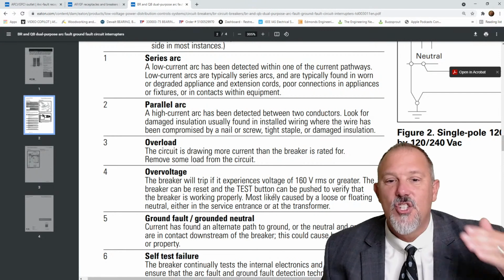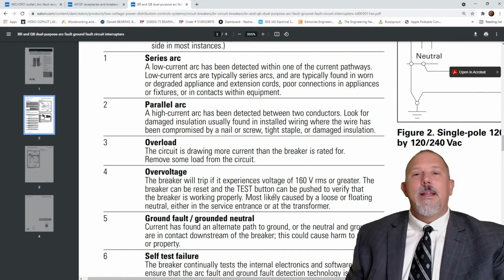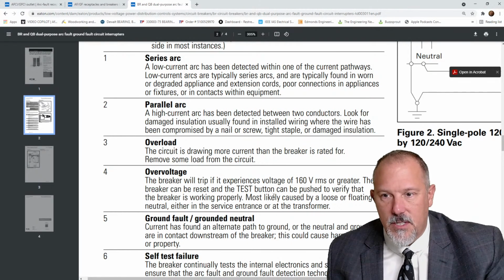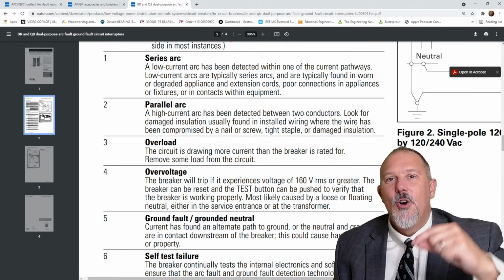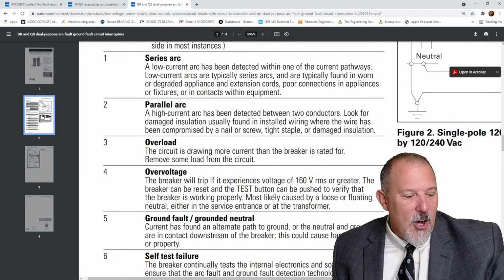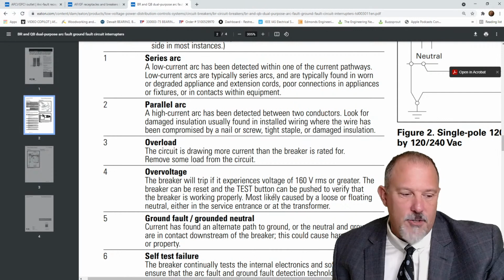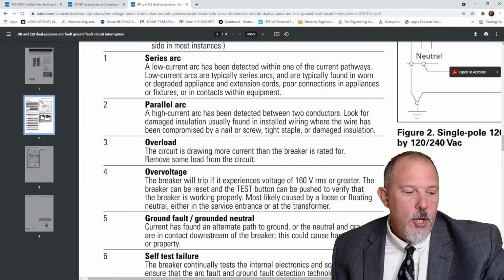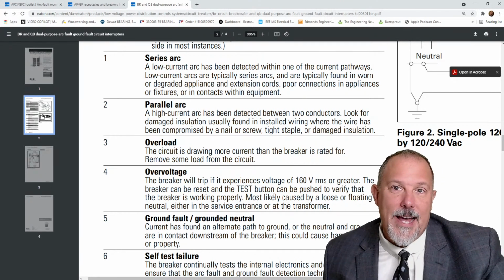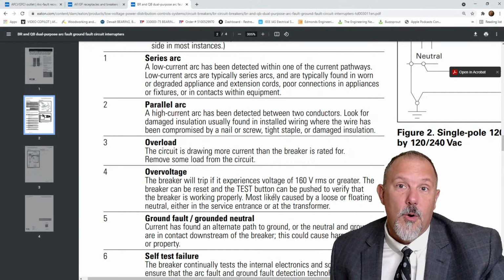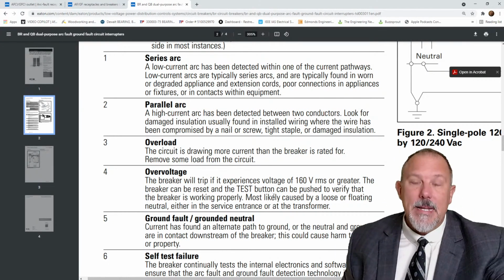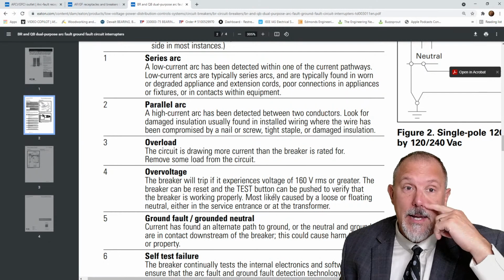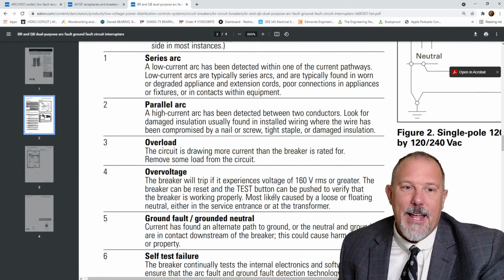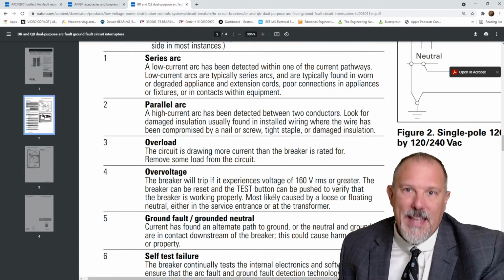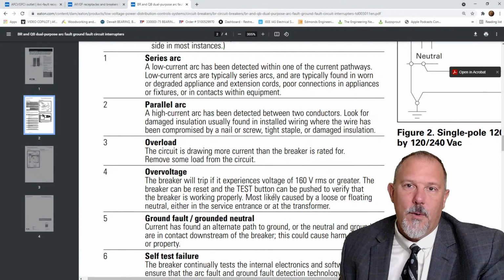And I'll tell you why this is so important. I used to be product line manager for these solutions. And I'll tell you, I would get phone calls where this is what they would do. They would say all of my breakers would instantly trip when energized. And I'd say, well, there's a problem with them. So I had a contractor, I don't know how many houses they had, all of their circuit breakers were damaged. We had to replace them. And I'm thinking, what is the issue that we got here? Why? The way they connected the house, they connected it to where they didn't have the neutral.